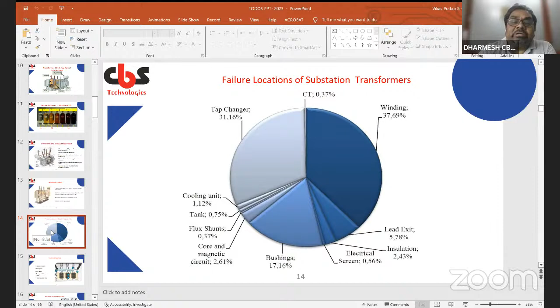How does moisture ingress into this transformer? This could be residual moisture. This could be atmospheric moisture. It could come through poor seals. It could come during installation or repair where the sealings are not done properly. And when all this moisture comes, it increases the moisture in the paper insulation.